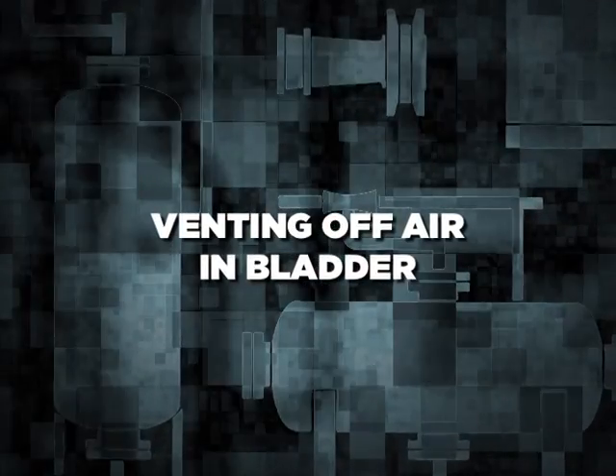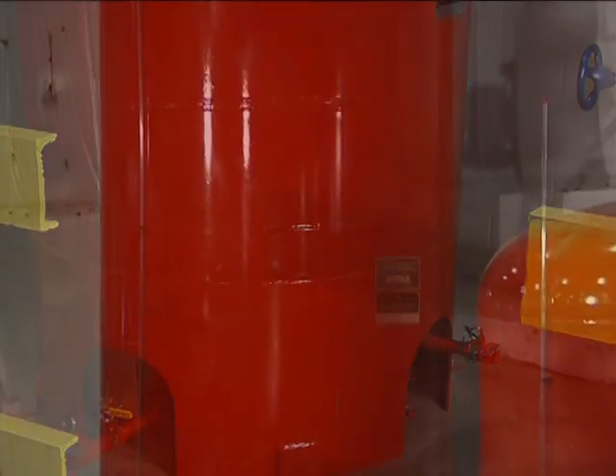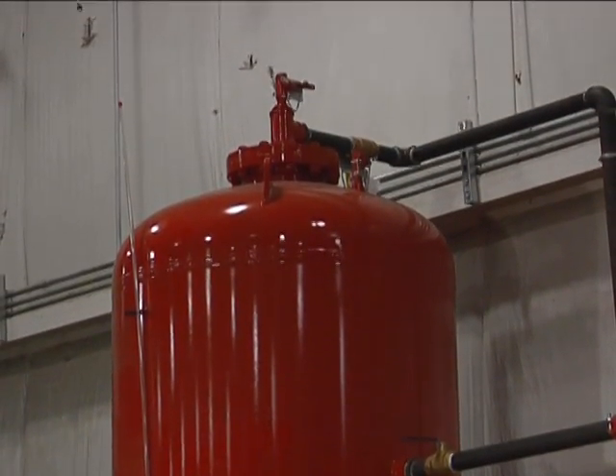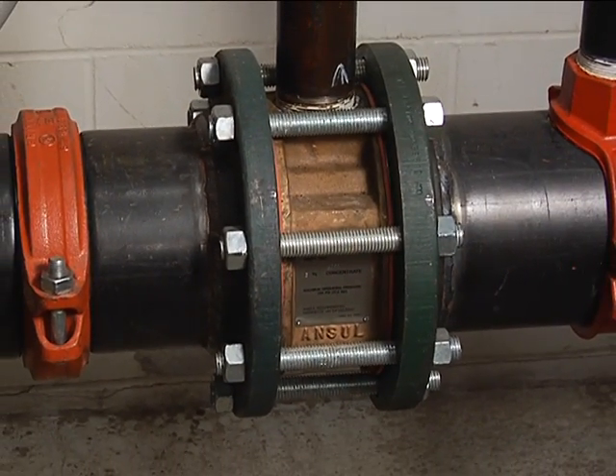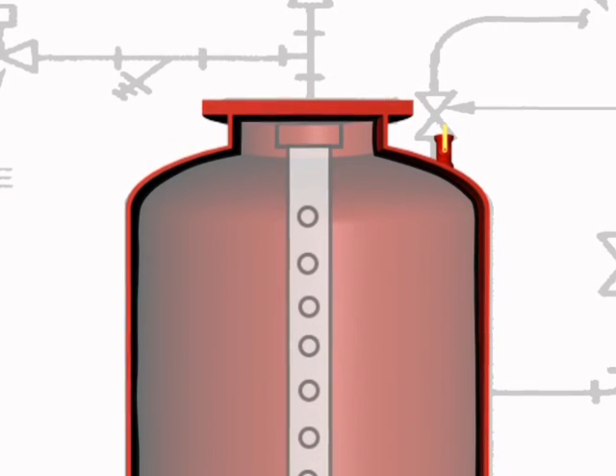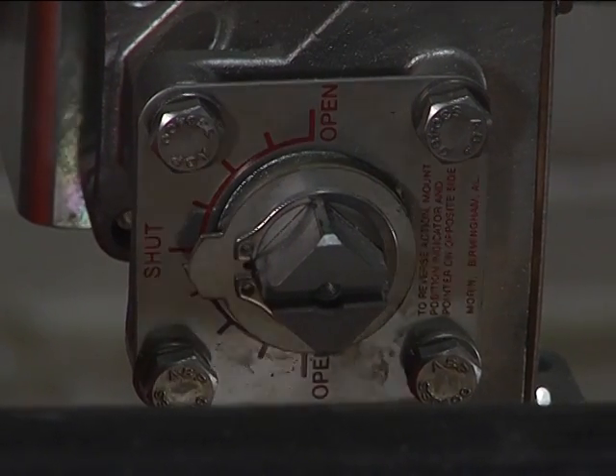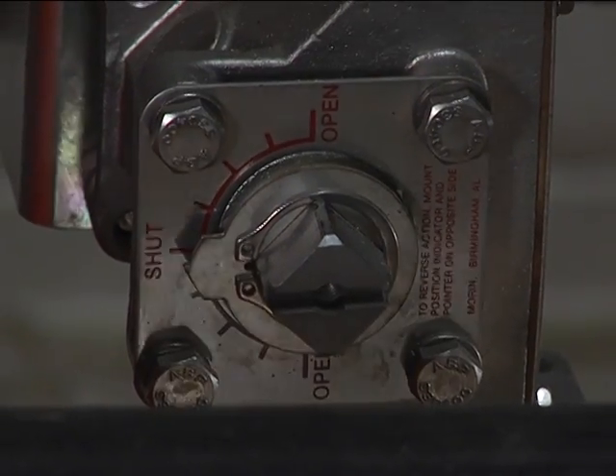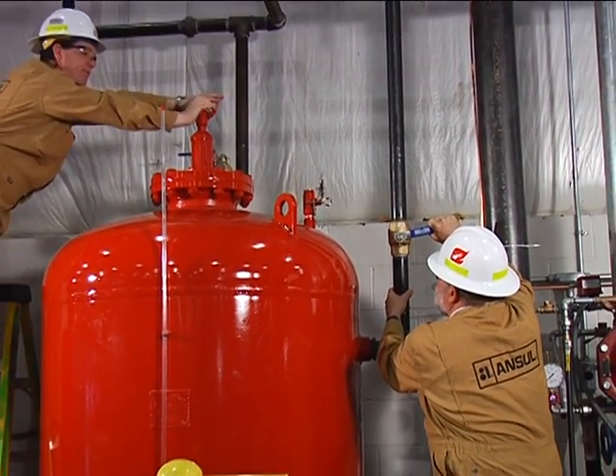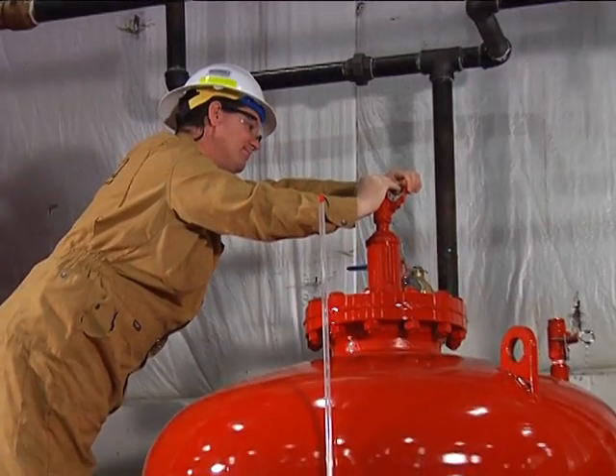Venting off air in the bladder. After filling the bladder tank with foam concentrate and prior to commission flow testing, ANSUL recommends venting any remaining air from the bladder tank. This ensures foam agent is available up to the foam concentrate outlet to ensure rapid response reaching the proportioner. To do this, very slowly partially open the water inlet valve with the tank shell vent valve open to vent air from the bladder until all air is vented from the tank shell and water appears from the tank shell vent valve. Make sure both the foam concentrate isolation valve and the hydraulic actuated concentrate valve are in the closed position to prevent loss of foam concentrate. Then close the tank shell vent valve and carefully partially open the bladder vent valve until frothy foam concentrate appears. Stand ready to close the bladder vent valve immediately so as not to spray foam concentrate over the tank or personnel.